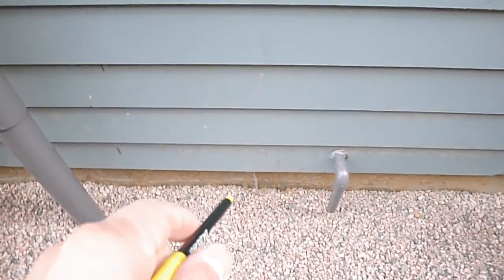So, this is where I tripped the front porch. I was checking the GFCI. Okay, this is the meter. It's below grade. There's one grounding cable. I'm looking for two, but I'm only seeing one. These butt seams, again, are all sealed, as they shouldn't have been.